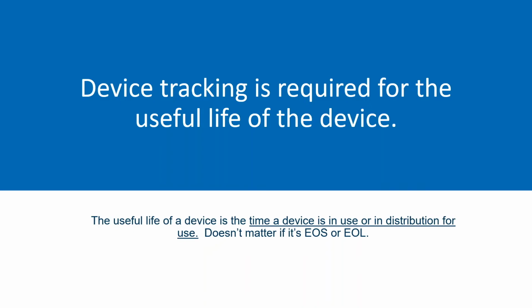What's the level of responsibility if the OEM has been fired, or there's a company buyout? That's in the regulation. The responsibility shifts to them. They still have to track the systems. It's not like all of a sudden, because they bought the whole caboodle, they have to do it too. We've had a few issues with that sort of acquisition process. But it doesn't change their obligation to still track it. So just remember that.